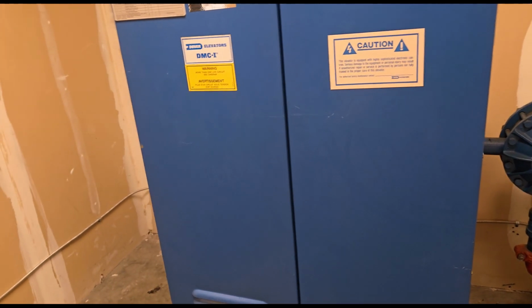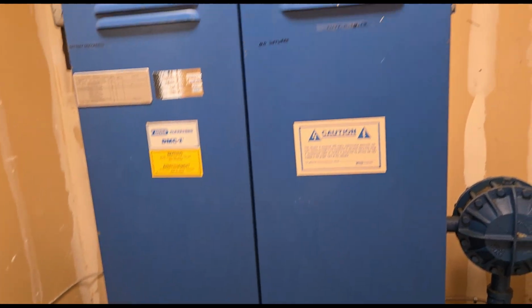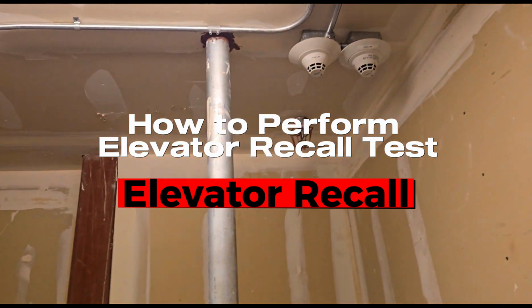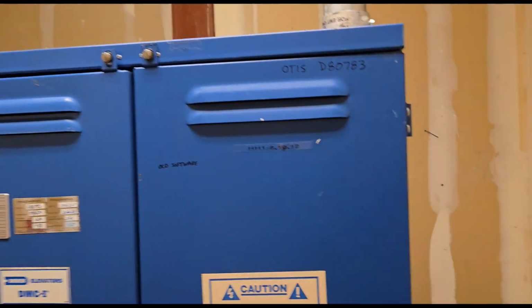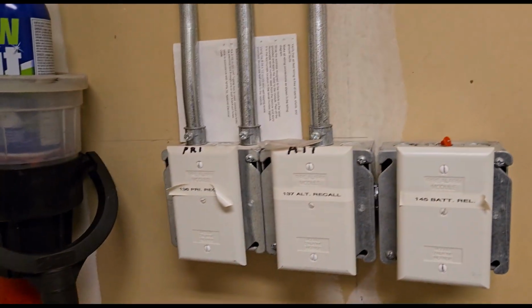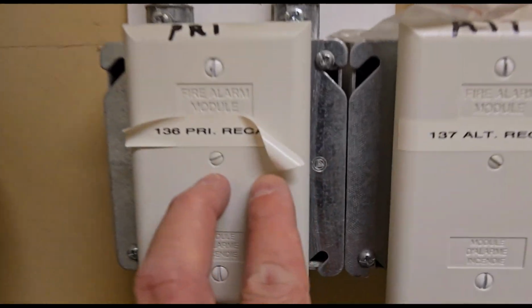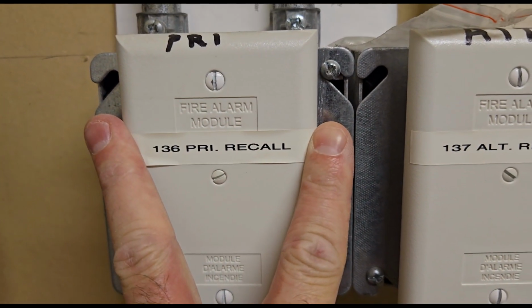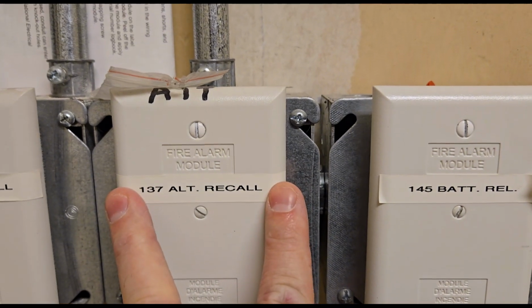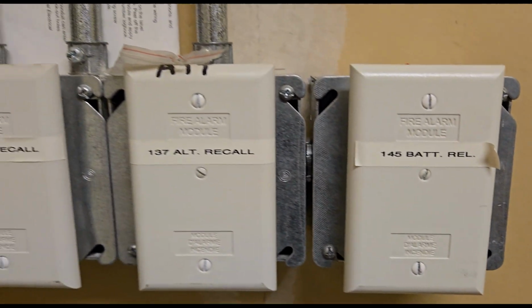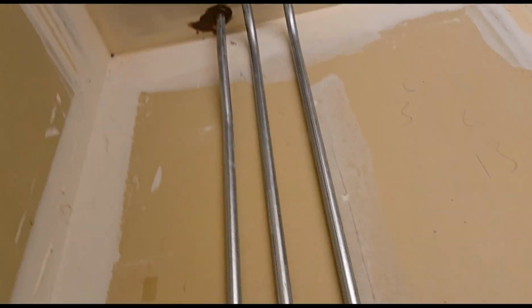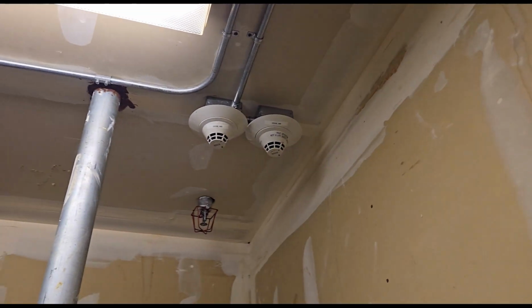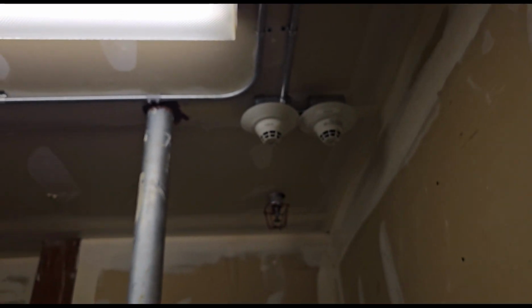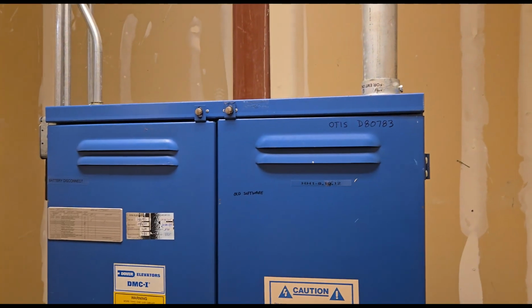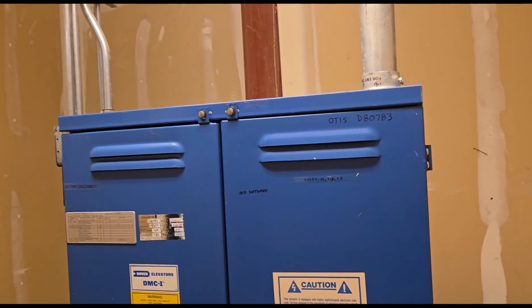In this video, I'm going to show you how to do the elevator recall test. So we're in the elevator machine room right now. We have our control modules for our primary recall and our alternate recall. And they will take control of the elevator after one of our devices gets hit, whether it's in front of the elevator, in the machine room, or in the shaft.